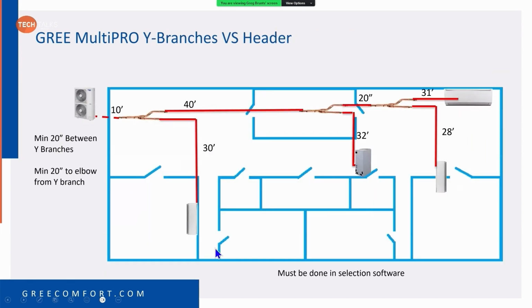All right, and there are some systems where it may be better for you to use a multiple Y branch setup. Again, that's going to be done in selection software so that we get everything right. But in this example, I have a layout: you've got 10 feet to your Y branch, you've got 40 feet between there and that Y branch. That pushes this Y branch way to the other end so that I only have 32 feet to this indoor unit. And then I've got my 20 inches to that Y branch, and I'm at 31 feet and 28 feet here. So all of my indoor piping stays below that 49-foot range, and you don't have to worry about upsizing pipe.